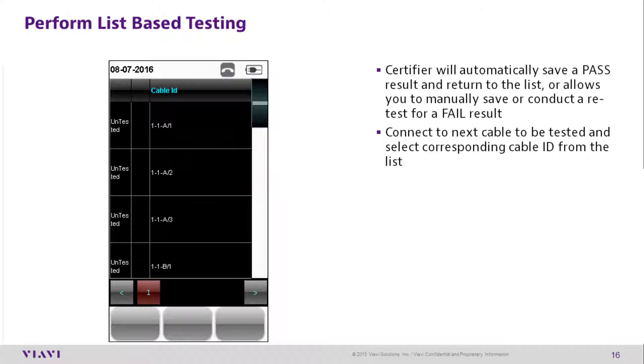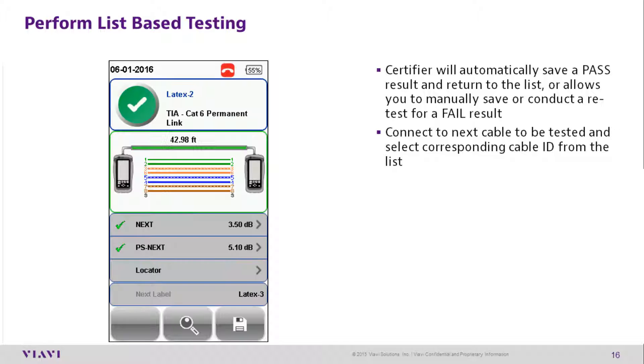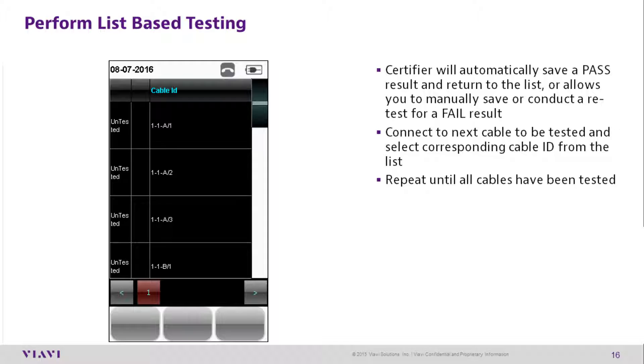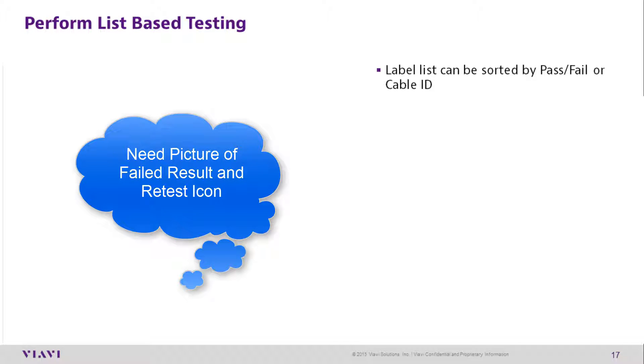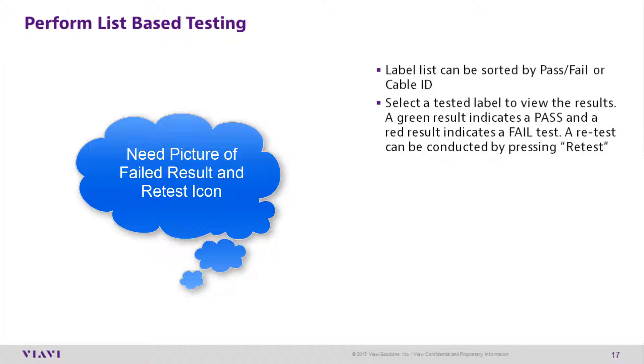Connect to the next cable to be tested and select the corresponding cable ID from the list. Repeat until all cables have been tested. Label lists can be sorted by pass/fail or cable ID. Select a tested label to view the results — a green result indicates pass and a red result indicates fail. A retest can be conducted by pressing Retest. Press the Auto Test button to return to the list.